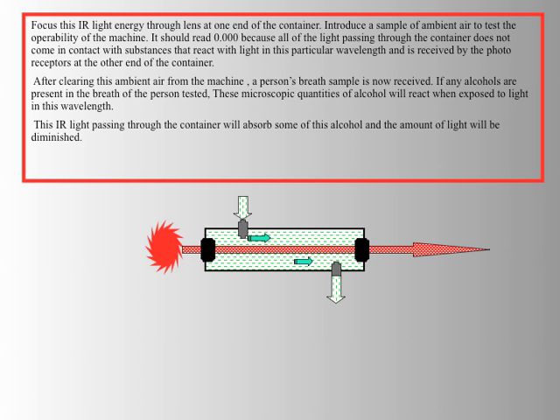When the machine is first queued up to measure a subject sample, the first thing that happens is a blank sample is passed through. That blank sample should contain no alcohol whatsoever, and the measurement should read 0.00 because there isn't any alcohol in it. After that, the subject blows into the machine and then the light is shined through again.